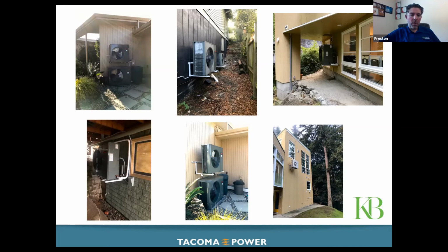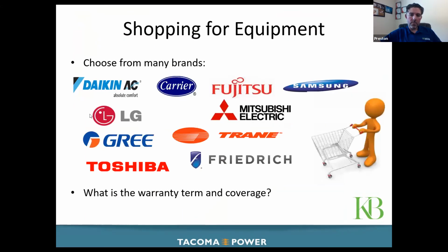It's not common practice to put them on wall brackets in our area. I try to avoid wall brackets if at all possible, and would rather put them on a pad on the ground. There are vibration corks that we put underneath the unit onto that bracket, and on the bracket to the house. But these units do vibrate, and you can get sound because that bracket attaches to the studs inside the wall of your home. So I try to avoid wall brackets if at all possible, because you can get noise and vibration coming inside the home. I like to put them on a pad if possible, but you can put them on wall brackets.